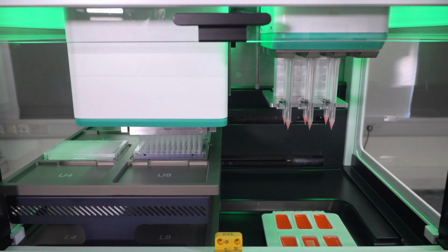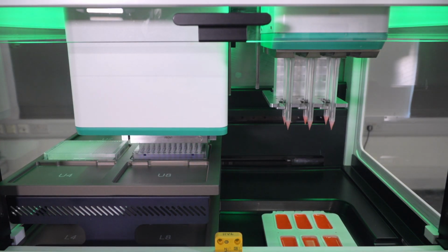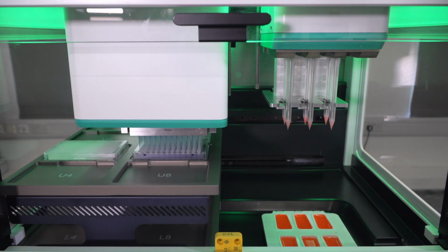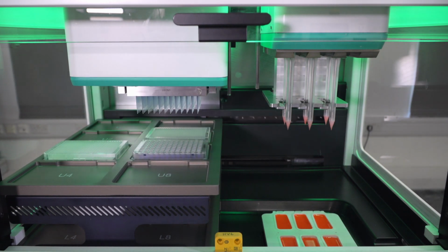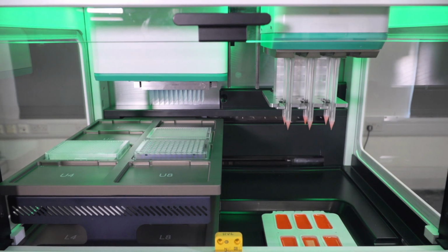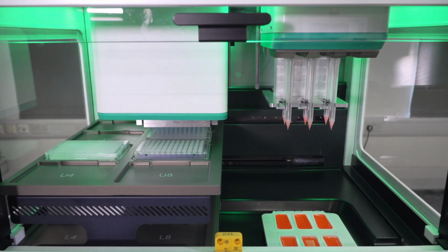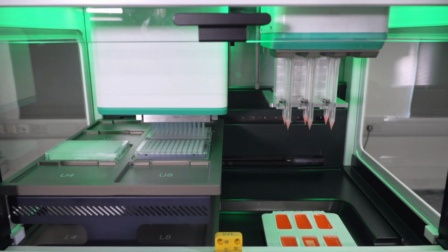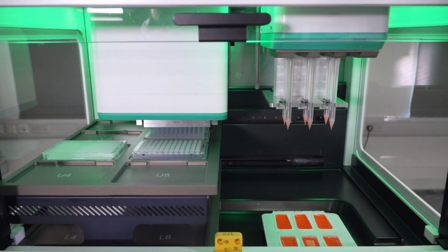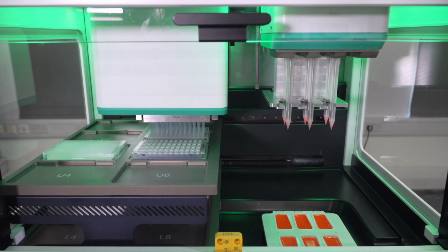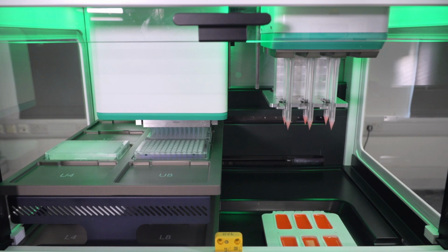So now it's going to go in and aspirate from that combination of the blue sample and the master mix that's just been added. We could add a mix cycle here if we liked, but actually the jetting from the dispenser is quite effective at mixing. So we've taken a sample now and we're going to quadrant that out into a 384 well plate. We're just using the tip touch feature there as well, so we ensure that the droplets of the dispensed sample touch off into the plate.